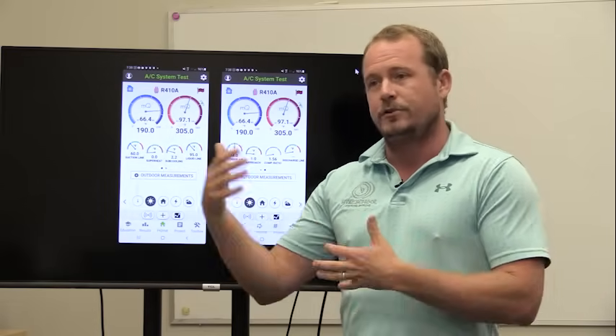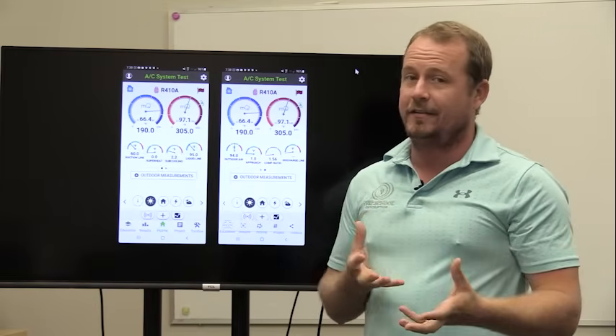But you also have rotary compressors, you have scroll compressors. In those cases, you could have significant wear inside the compression chamber that could cause it. We know with a scroll, you've got your stationary scroll on top and then you have your oscillating scroll on the bottom. And so if there's a lot of gap between those where they fit, that could cause it. But actually, most commonly, what causes poor compression is actually safeties.